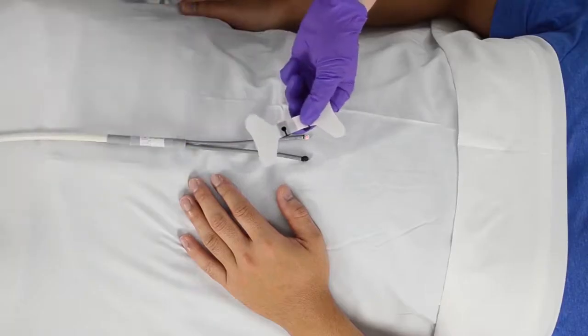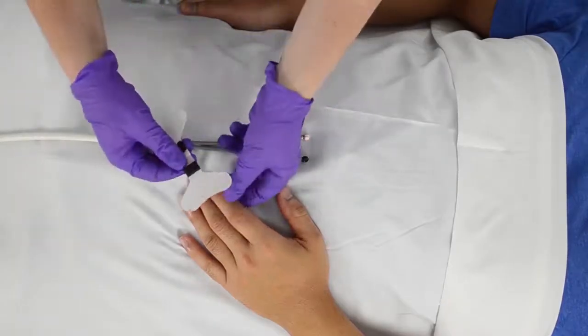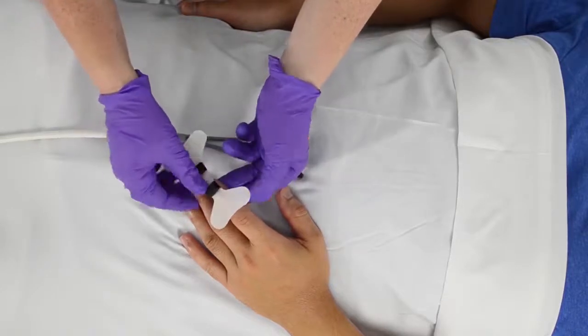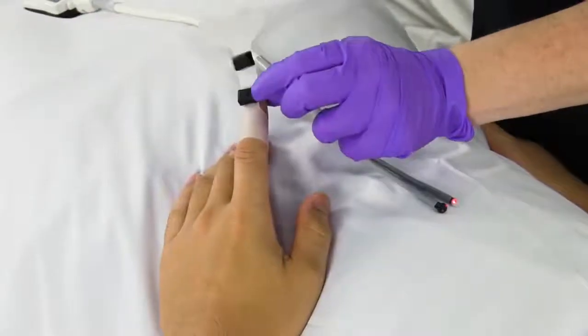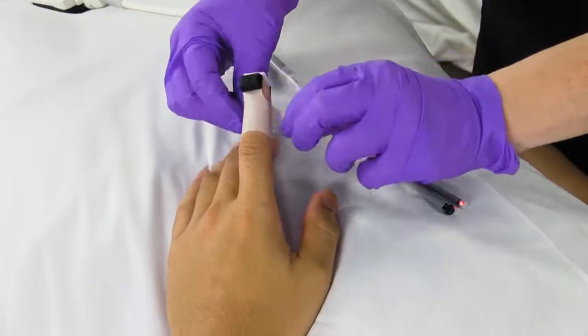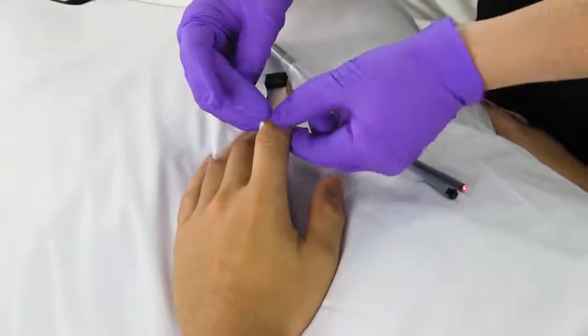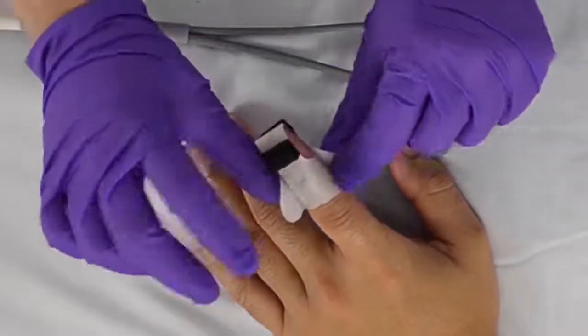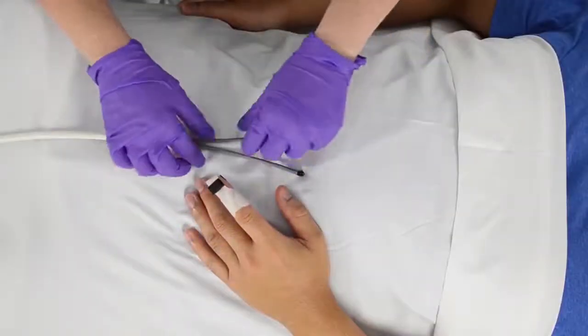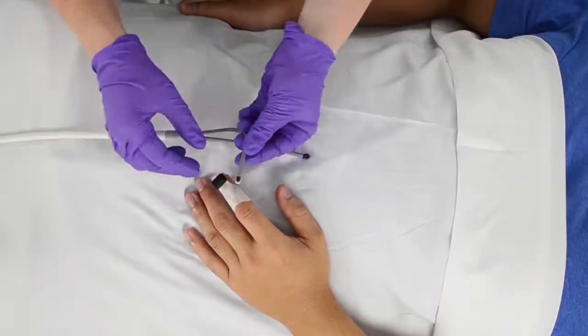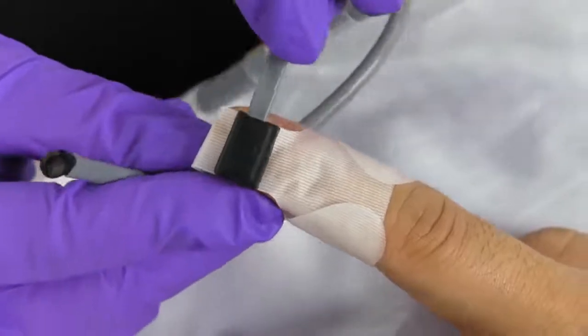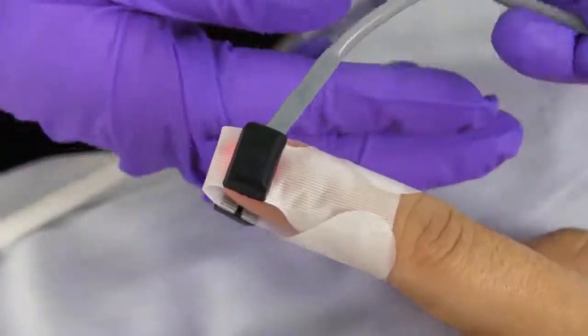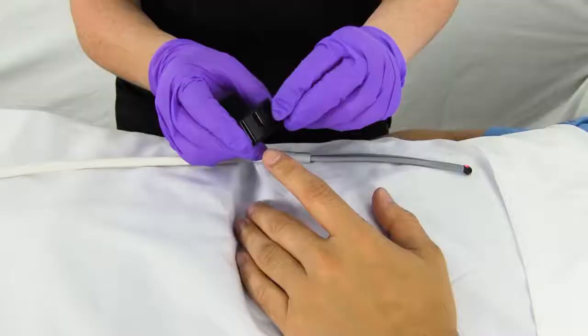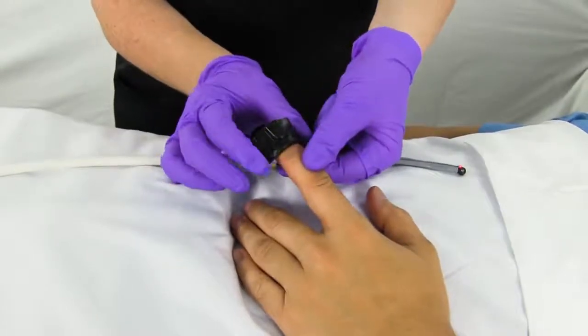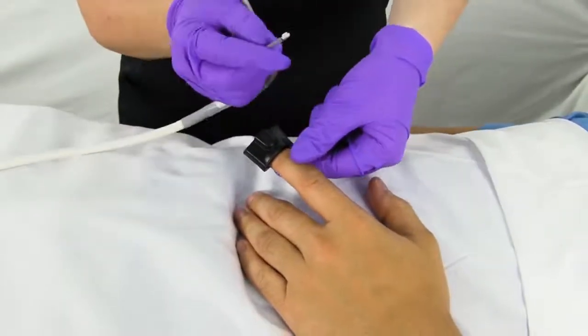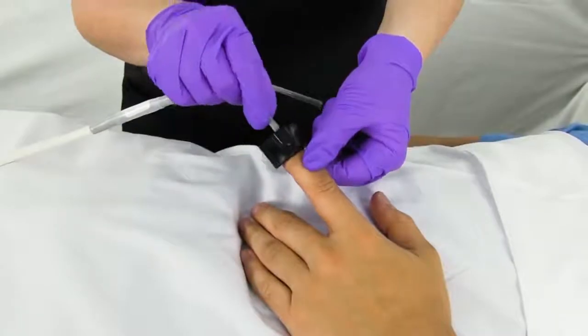To apply the adhesive secure grips, peel off one side and align the sensor over the nail bed and stick it down. Peel off the other side and wrap it gently around the other end, ensuring the black rubber ends are opposite. Gently fold remaining tape around the digit as shown. The user must be sure the grips are secure as to avoid poor readings. The user needs to ensure they do not wrap too tightly and check circulation after applying the grip to the patient. When applying the reusable grips, slide the sensor over the selected digit and position the number icon so it is directly over the patient's nail bed.